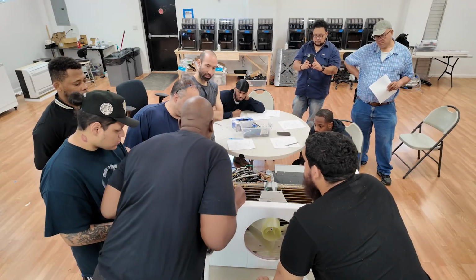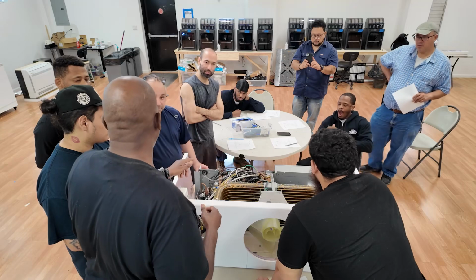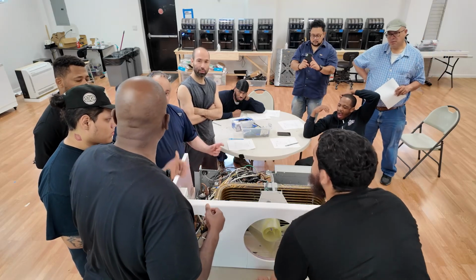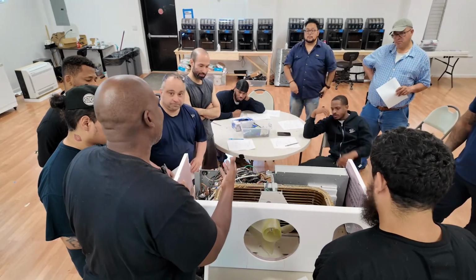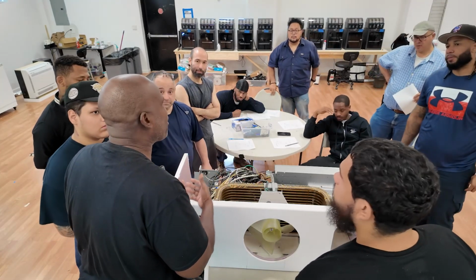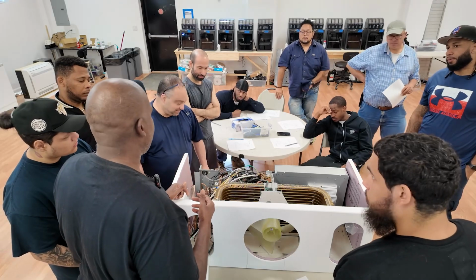What is the bottom of the compressor? That's just the heat, to keep it warm? Yes, to keep it warm, to boil the refrigerant out of the oil. Oh, the oil. So that's a compressor heater, right? Sometimes the old school term is crankcase heater, but we don't have a crankcase here, so it's just a compressor heater. That's a crankcase heater. I remember that.